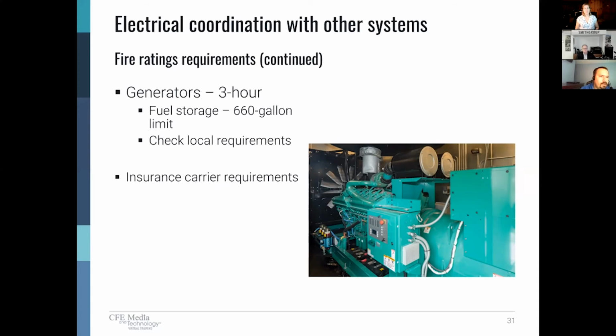And then interior generators also require a 3-hour rating around the room, and the fuel storage capacity within that interior of the building, within that room, is limited to 660 gallons. It's also obviously important to check with your local amendments or adjustments to code or local interpretations. The national codes aren't always the end-all be-all in every jurisdiction. And then of course you've got insurance carrier requirements such as FM Global, for example, and they may have some very specific requirements that are nuances that you have to watch out for as well.